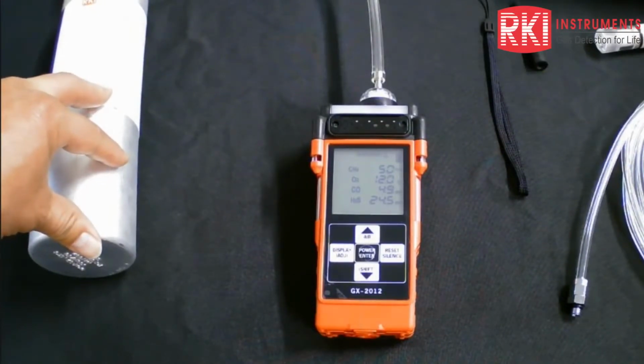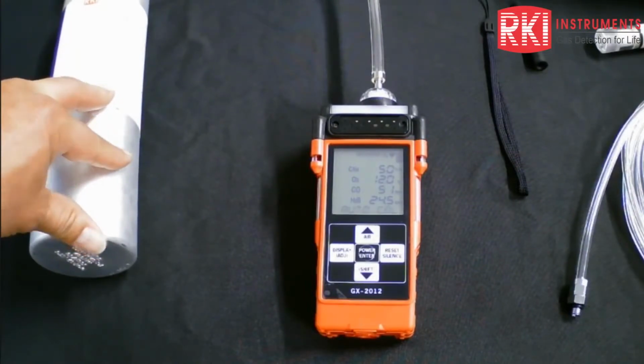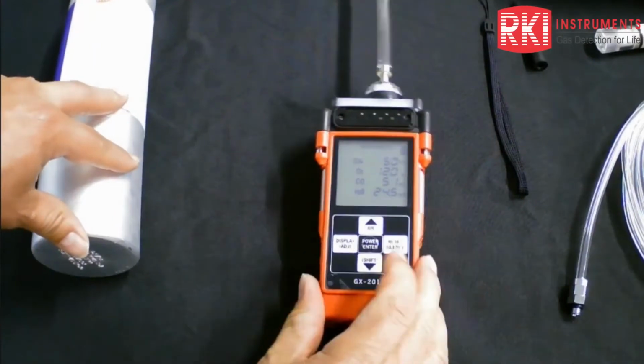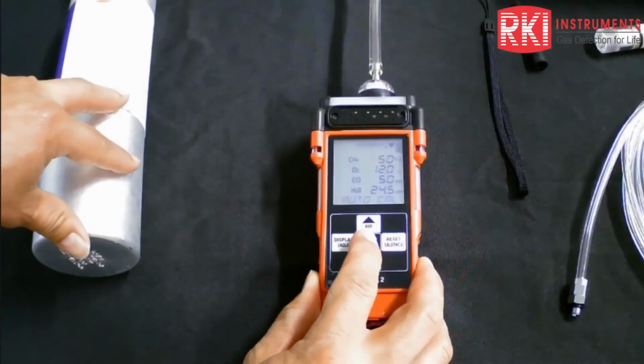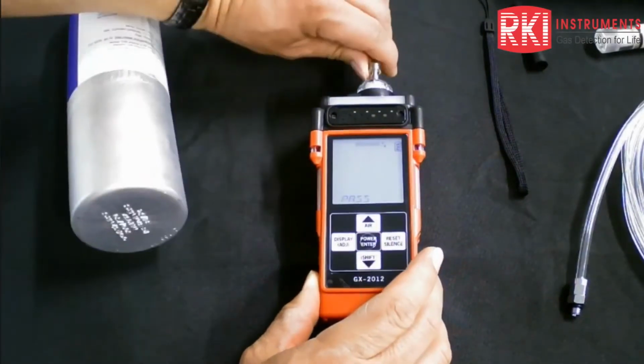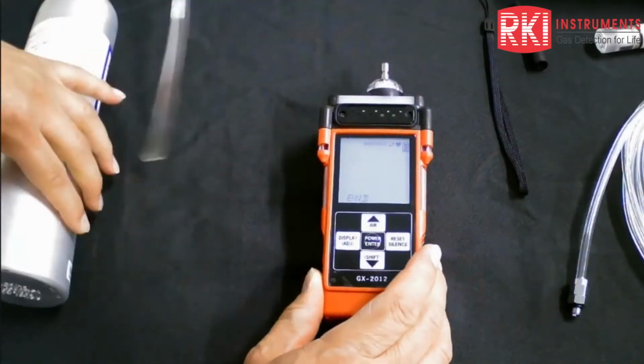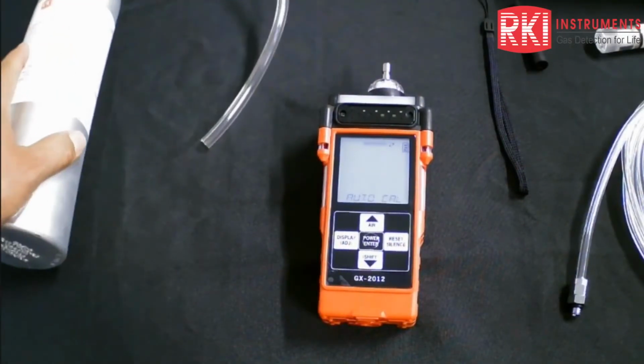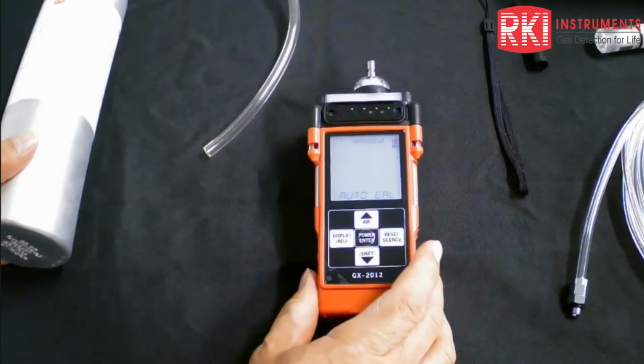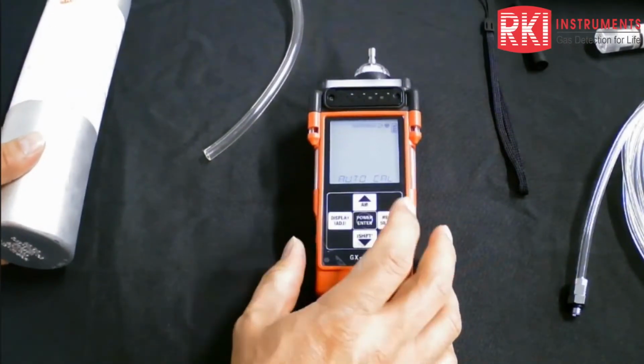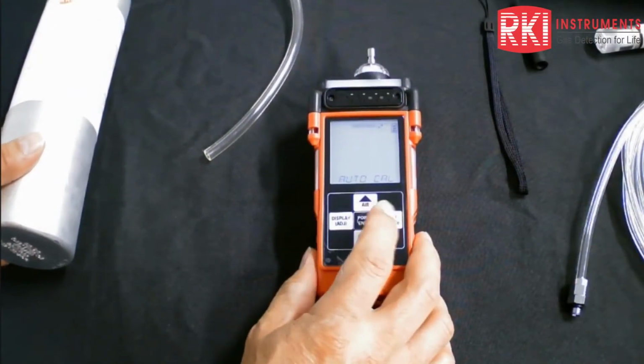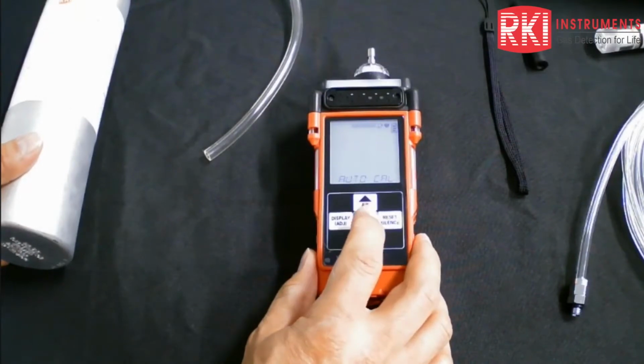Okay, so we're just going to flow that gas a bit longer, and the readings may go up and down just by a value. Okay, so it's pretty good there, fluctuating up and down. Okay, so that's fine. So at this point, I'm going to press the power button, pass, take the gas off. Okay, and then it's back at auto cal. I'm going to go back into auto cal again.